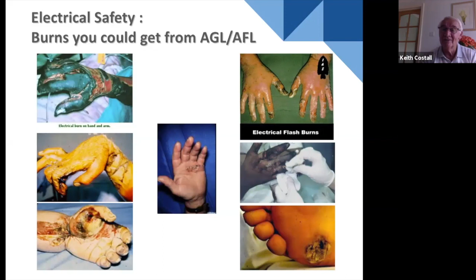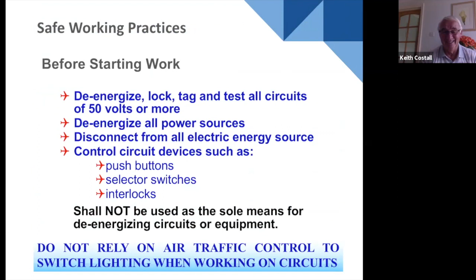So before starting work on AGL, de-energize, lock off, and test circuits to check that they're dead. Anything above 50 volts, that should be done. And we make sure the system is de-energized from all the potential power sources. And one of the things that we can have in AGL is cross feed between circuits. So that's why it's important to earth down. And do not rely on the air traffic controller to switch off for you. Please do not, because that is asking for trouble.